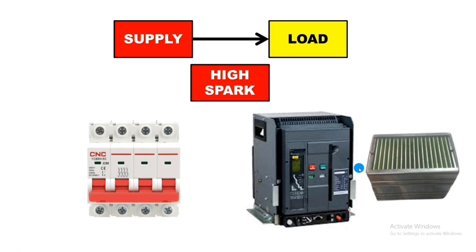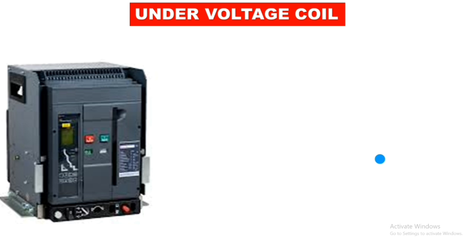To quench or reduce this high spark, an arc chute is connected in the air circuit breaker. Because the make and break process in an air circuit breaker is done at a very high amount of current, a very high spark is generated. So the arc chute provides an external air medium to quench or reduce this high spark. Arc chutes are not required in MCBs and MCCBs.